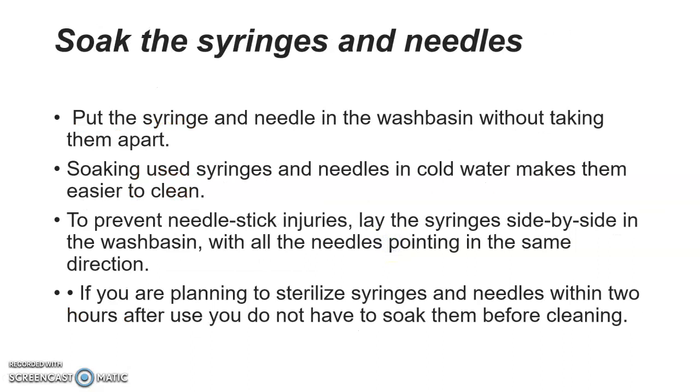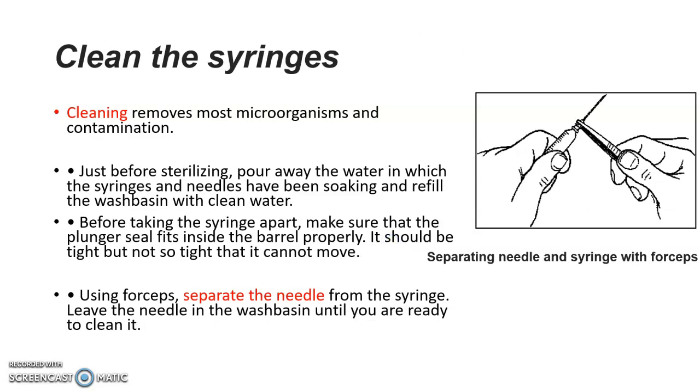Now next is soaking the syringes and needles. After flushing, we should put the syringes and needles in the wash basin without taking them apart. Soaking used syringes and needles in cold water makes them easier to clean. To prevent needle stick injuries, lay the syringes side by side in the wash basin with all the needles pointing in the same direction. If you are planning to sterilize syringes and needles within 2 hours after use, you do not have to soak them before cleaning.